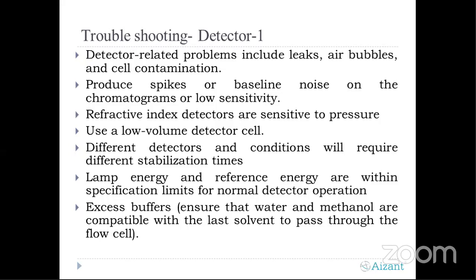Second problem with the detector: you said there are a lot of spikes in the baseline noise because of low sensitivity. Refractive index detectors are sensitive to pressure. We know that a refractive index detector is a bulk property detector. It's not related to any chemistry of the molecule or the absorption of any wavelength. It's simply a bulk property. It's the deflection of the detector from the baseline, which the detector will monitor and will quantitate the sample.